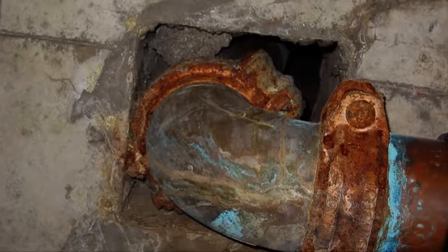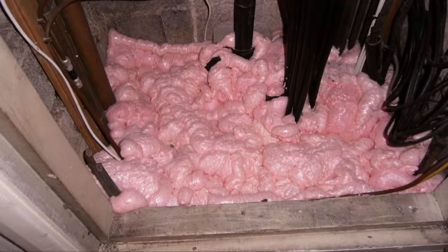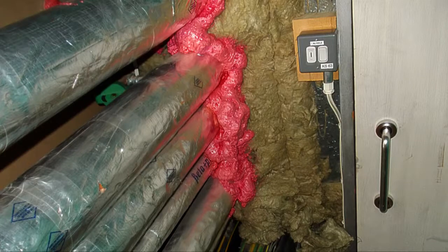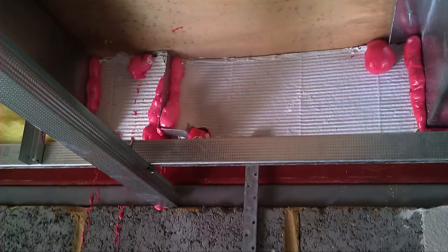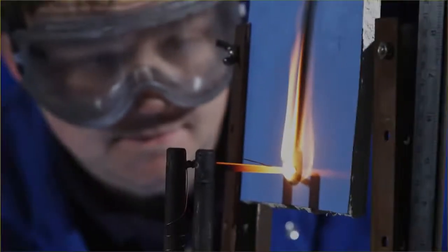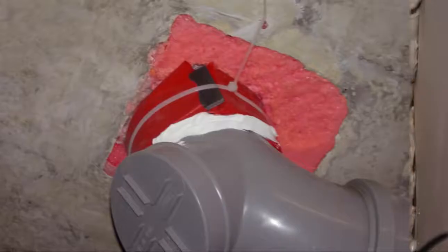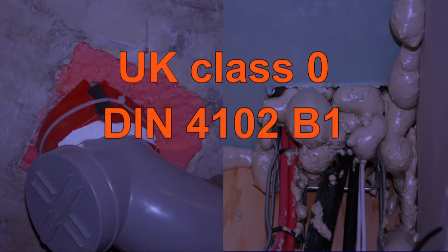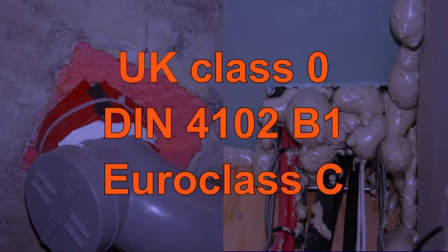One such example, which is increasingly being observed, relates to the inappropriate use of so-called fire-rated polyurethane, PU, foams. There are two issues. Firstly, they are sometimes sold on the basis of their performance in less severe reaction to fire tests. Such foams may be coloured to indicate a performance, such as UK Class 0, German DIN 4102 B1, or Euro Class C. These performances are no indicator of their ability to seal openings in compartment walls and floors with cables or pipes passing through them.